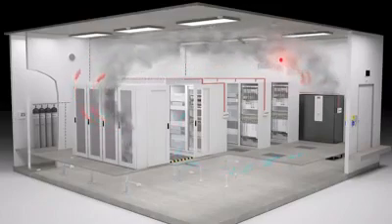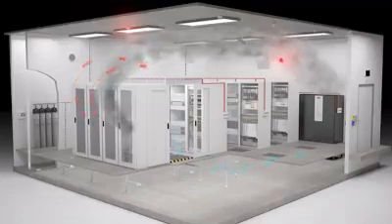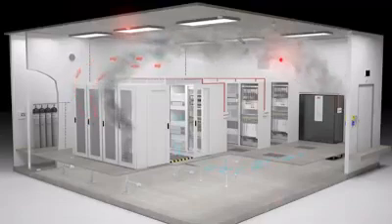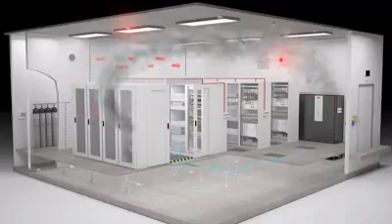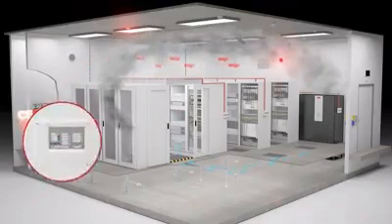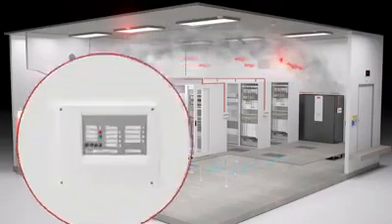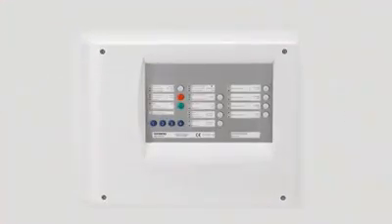As additional smoke develops, the point-type smoke detector triggers a fire alarm and signals to the extinguishing control panel. The extinguishing control panel shows that two zones are in alarm state.